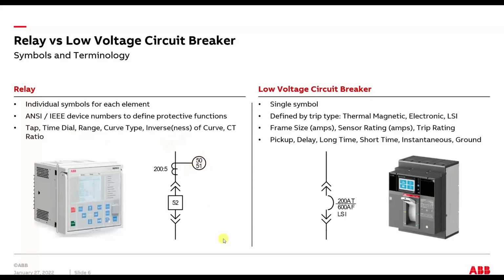Yeah, this is actually an important slide, because it goes through one of the big things I'm trying to convey in this presentation, which is this terminology. For a protective relay, the settings are called tap and time dial. They use the terms range, curve type, inverseness of a curve, and CT ratio.